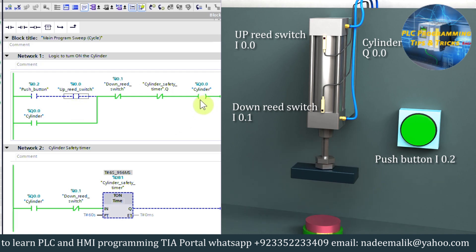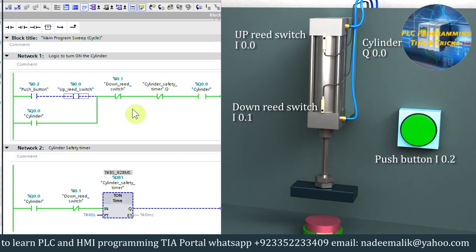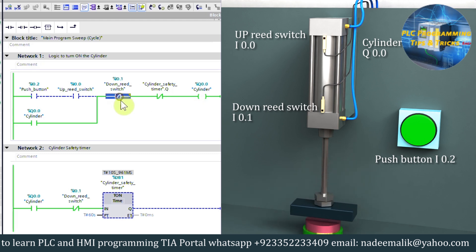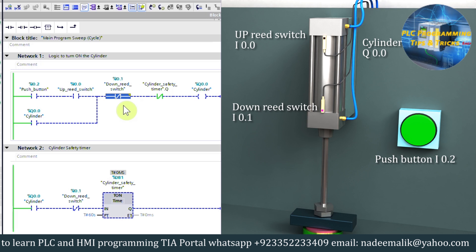As the cylinder reaches the down reed switch sensor I0.1, this contact opens and unlatch the cylinder output Q0.0. As cylinder starts to go back to the up position.